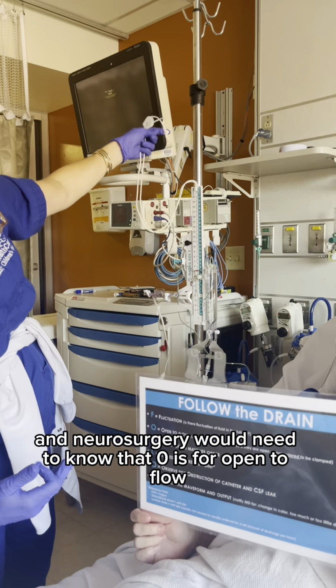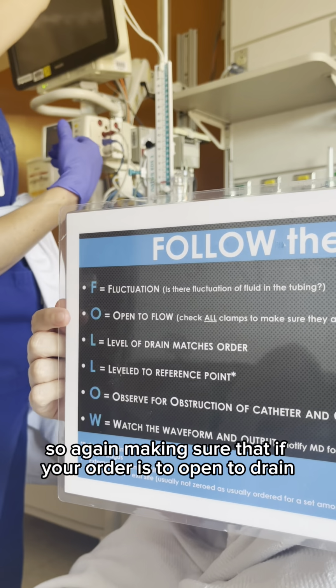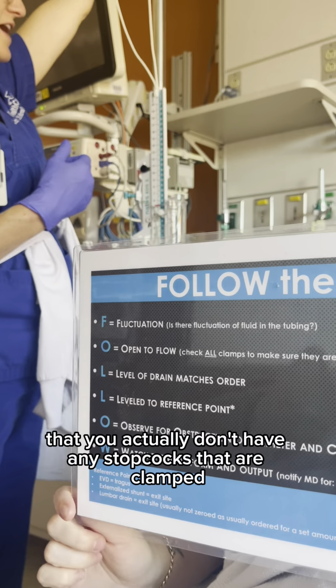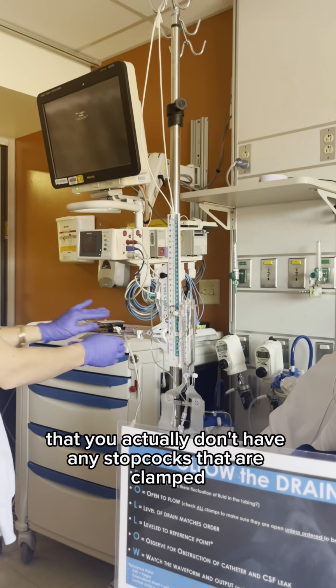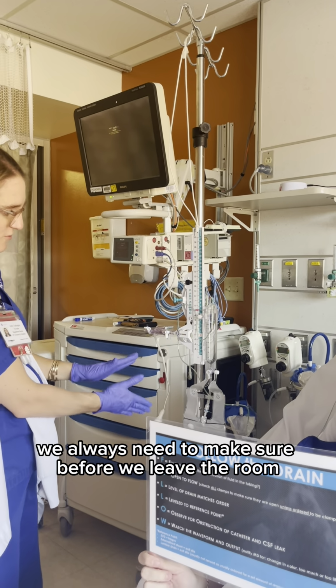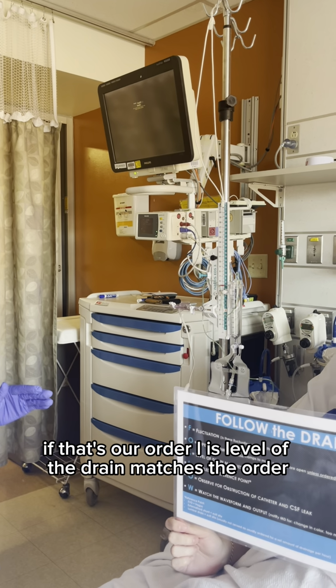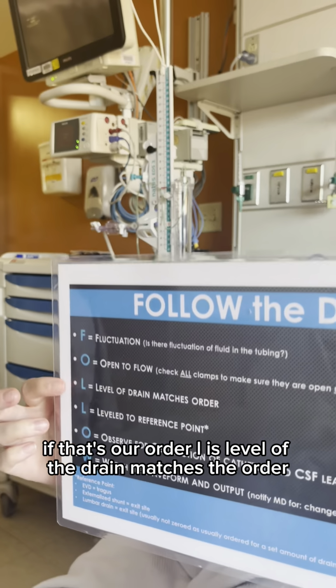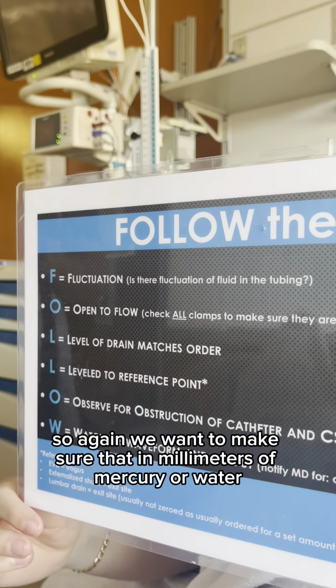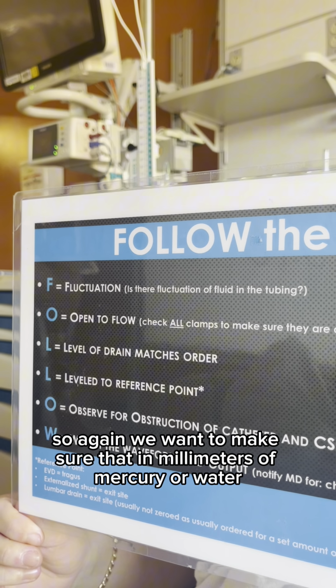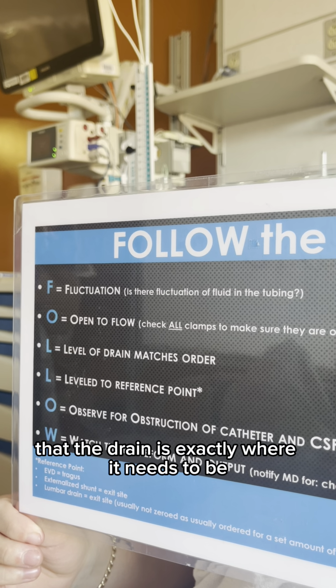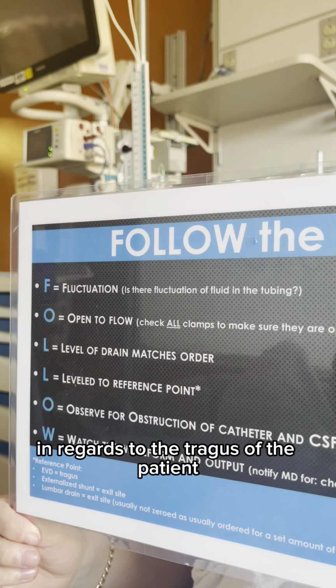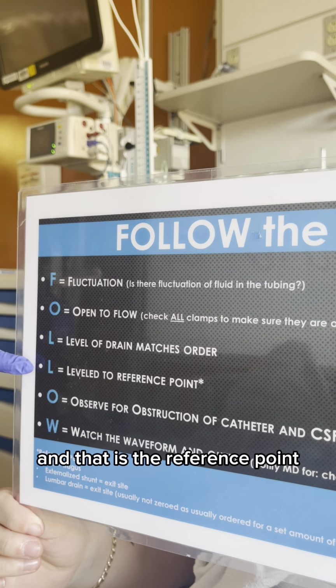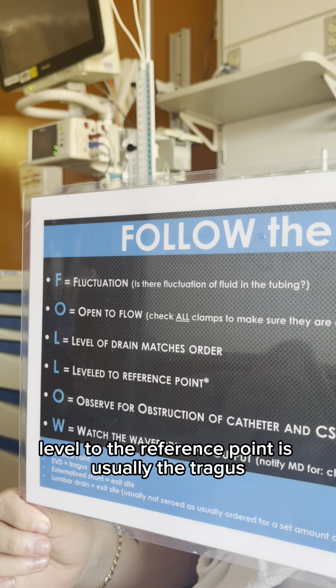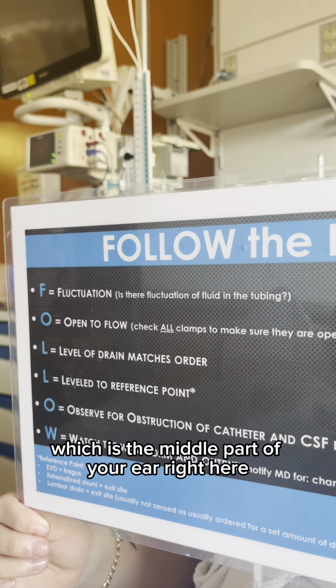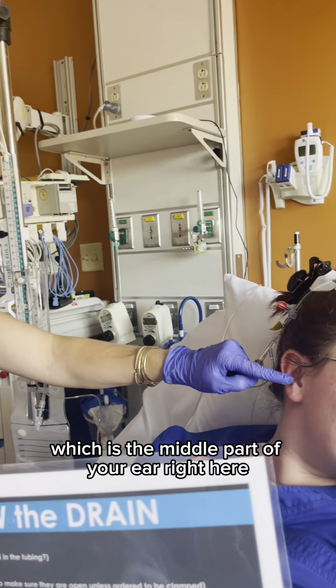O is for open to flow. So again, making sure that if your order is to open to drain, you actually don't have any stopcocks that are clamped. We always need to make sure before we leave the room that we are open to drain if that's our order. L is level of the drain matches the order. So again, we want to make sure that in millimeters of mercury or water, the drain is exactly where it needs to be in regards to the tragus of the patient. And that is the reference point. Level to the reference point is usually the tragus, which is the middle part of your ear, right here.